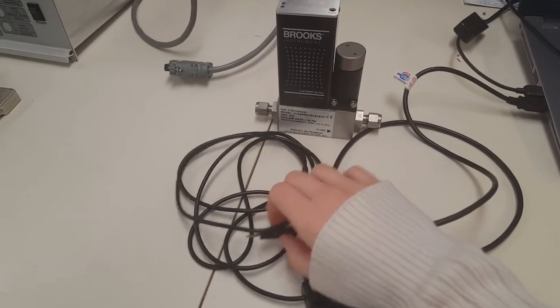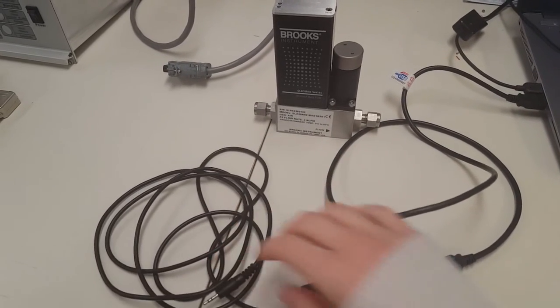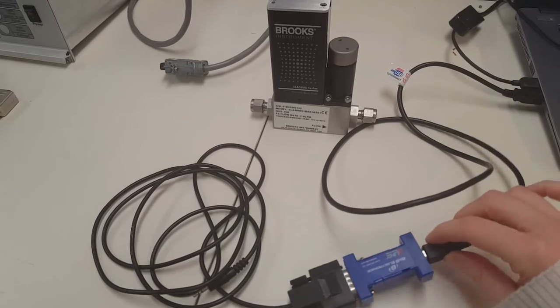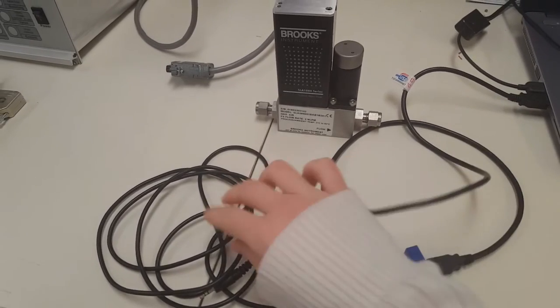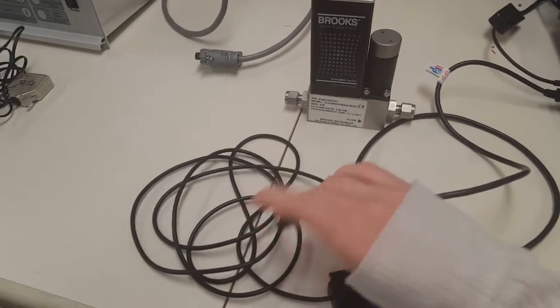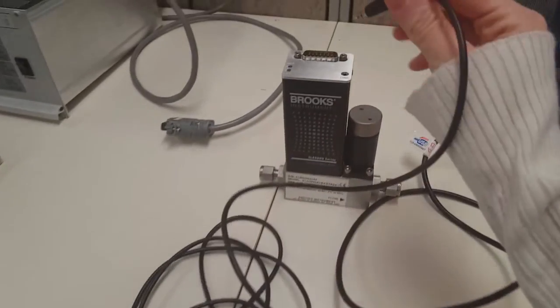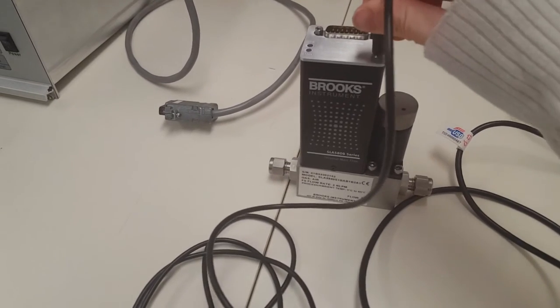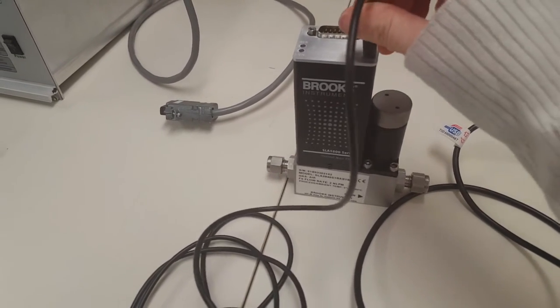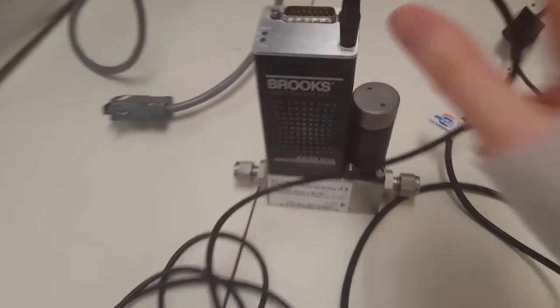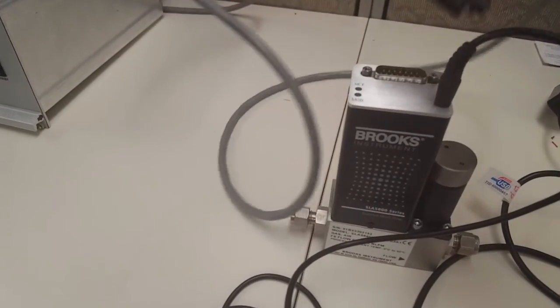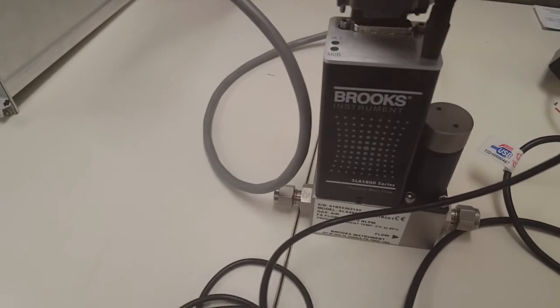Ensure the RS-232 side is connected to the computer. Insert the 2.5 millimeter jack plug into the device's diagnostics port labeled Diag on the device. Verify that the device is powered on and the MOD LED is solid green or flashing red.